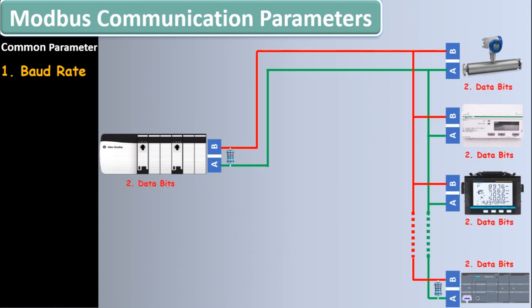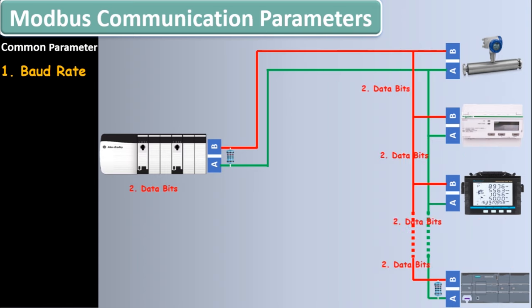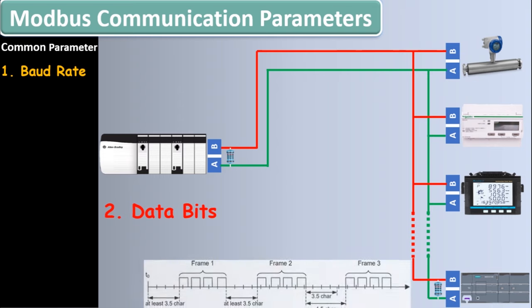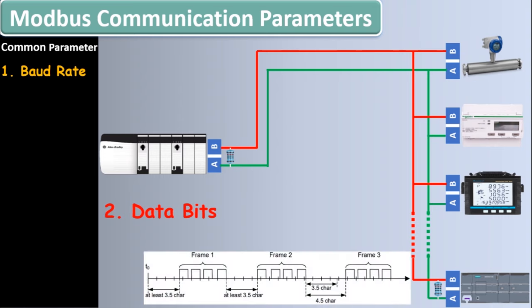The second common parameter in RS485 communication is the number of data bits. All devices in the same RS485 network must have the same number of data bits. Data sent across the Modbus network is in the form of frames. There are two types: 7-bit or 8-bit digital frames. This is handled internally by the RS485 communication port. Normally we use 8 data bits, and the frame shown in the picture is also 8-bit.